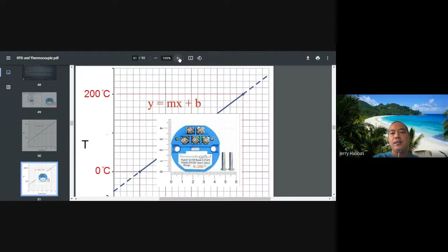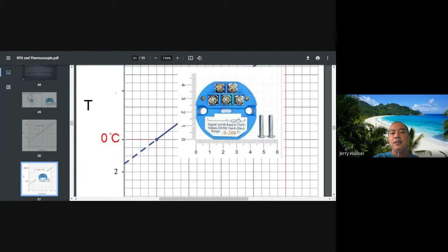Particularly, we recall the equation of the line, y equals mx plus b, where y is the vertical axis, x is the horizontal axis, which is the current, and m and b are the slope and intercept, which are constants. Okay, so for a temperature transmitter of 0 to 200, the output is 4 to 20 milliamps, within a certain range. So how are you going to compute mathematically? We should use the equation of the line.